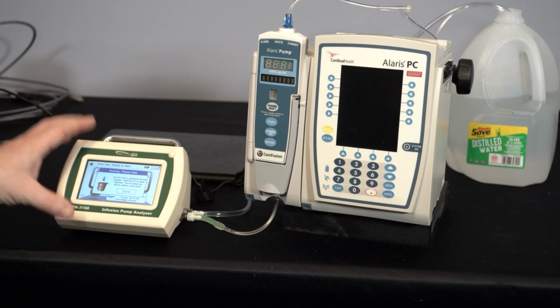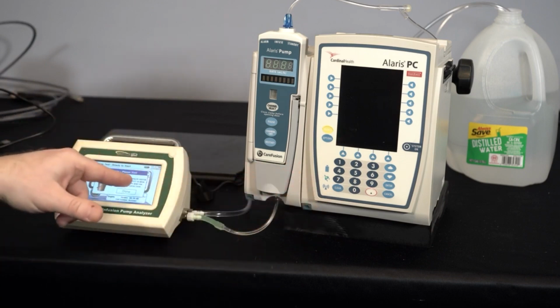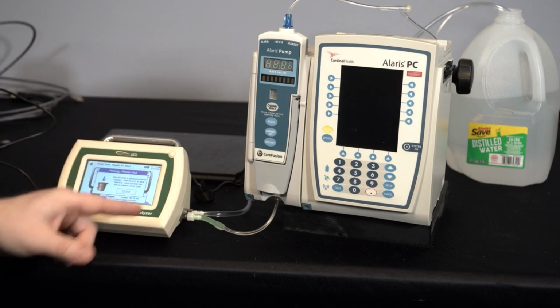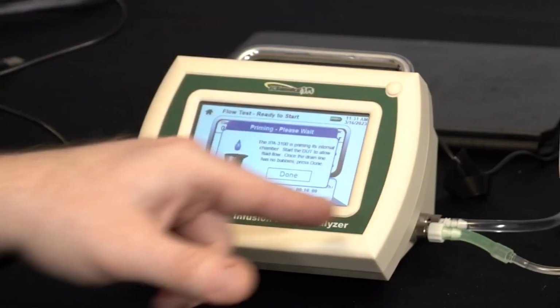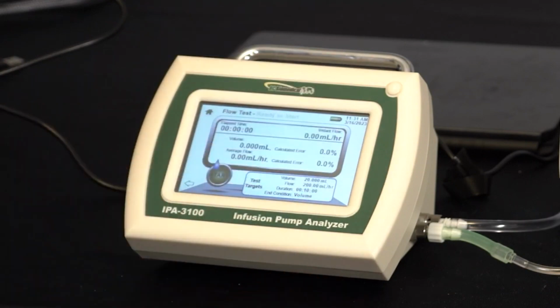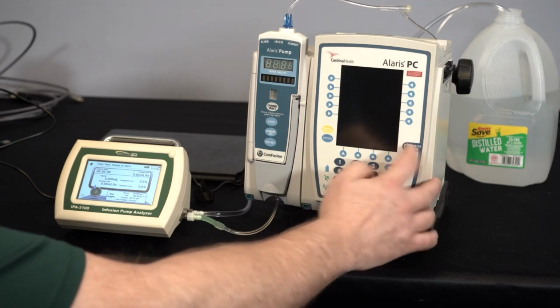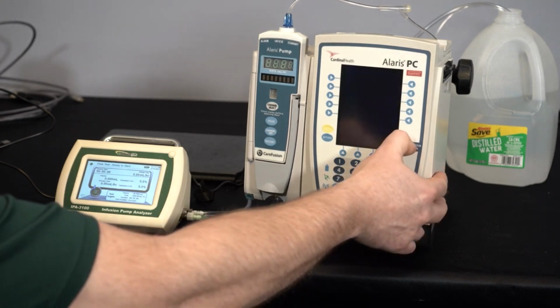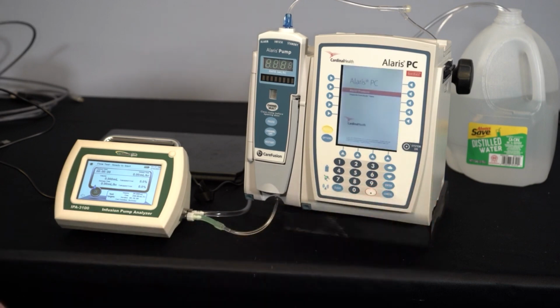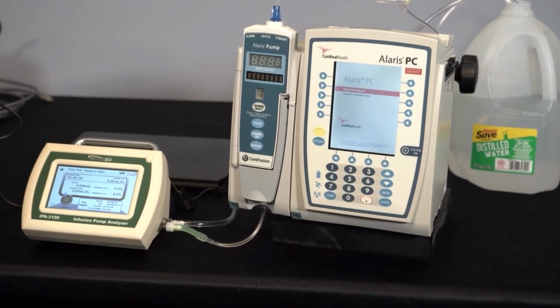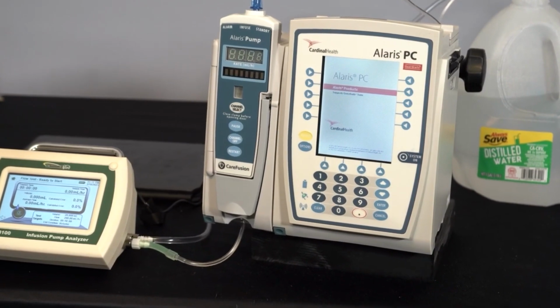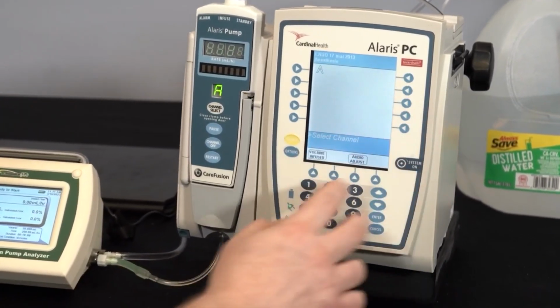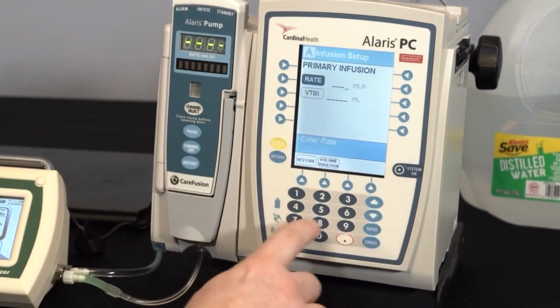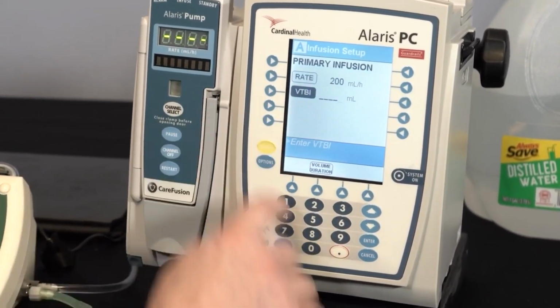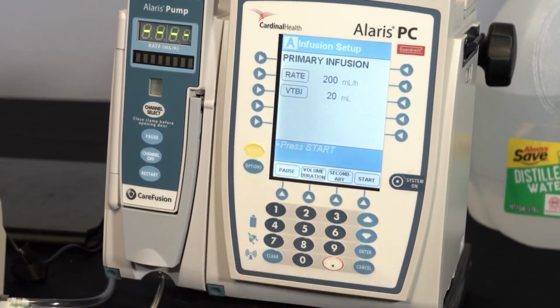So the IPA 3100 doesn't know that I primed, because I primed using the drain function, so I kind of tricked it. So now it thinks you need to prime. Well, we just did that, so prime is done, it's ready to go. And now we need to configure the infusion pump. So I'm going to turn that on here and configure the pump to match the settings that we have on the infusion pump analyzer. We're going to let the system boot up. And configure the channel. We said 200 milliliters per hour and 20 milliliters. And now it's ready to go.